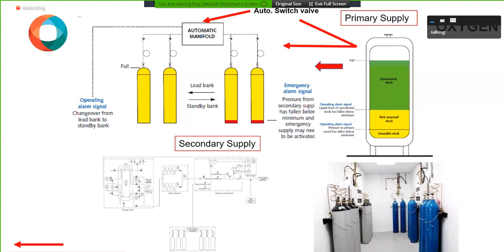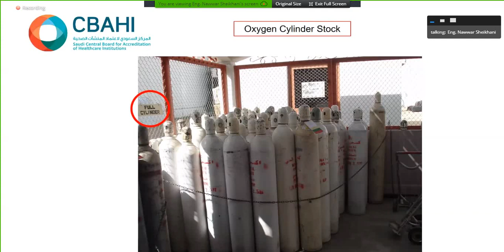However, the primary source, the secondary source, and the oxygen cylinder stock should all be available. Why should we have an oxygen cylinder stock since we have a manifold and a LOX tank? Actually, I put this slide in intentionally because it's wrong, to show you an improper storage. However, why should we have cylinder stock not connected to the manifold? What happened in some hospitals, in some cities, especially after an external disaster like the flood in Jeddah in 2010 and 2011, is that the supplier of medical gas was not able to provide hospitals with cylinders and liquid oxygen for 2 days. The hospital stayed without supply.